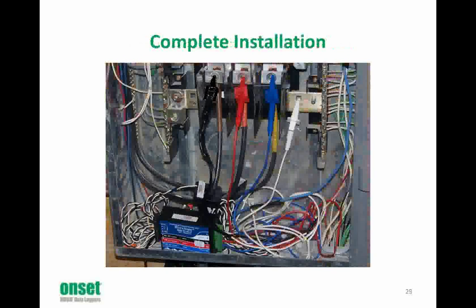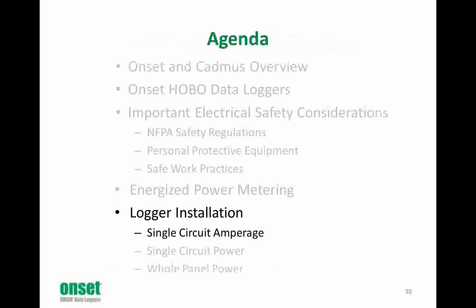Here is an example of a completed installation before the cables are organized. We can see the WattNode at the bottom of the enclosure, voltage leads on the appropriate phase conductors, and CTs right under each voltage lead. We will now discuss the installation of a simple current meter.